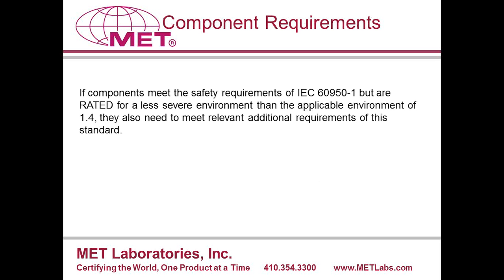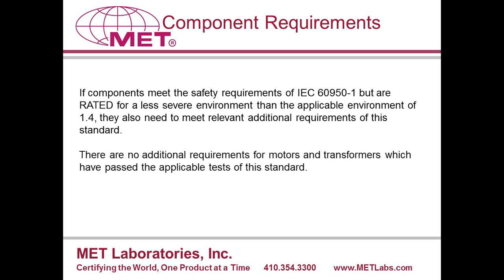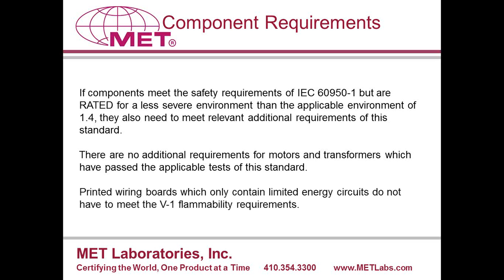There are a few changes to the component requirements that I want to make note of. The first is that a product that is compliant to a standard other than 61010 may not be sufficient. For example, you may have a 60950 power supply that is meant for a 2,000 meter environment, but needs to go into a product at high altitudes. This power supply would need further investigation. Similarly, a listed power supply would still need to be tested for dielectric strength after humidity. Now, on the other hand, motors and transformers do not have to meet component recognition if they can meet the requirements of 61010-1. Last, printed circuit boards no longer have to meet V-1 flammability ratings if they have limited energy circuits on them, such as the 5-volt 20-amp circuit that I discussed earlier.